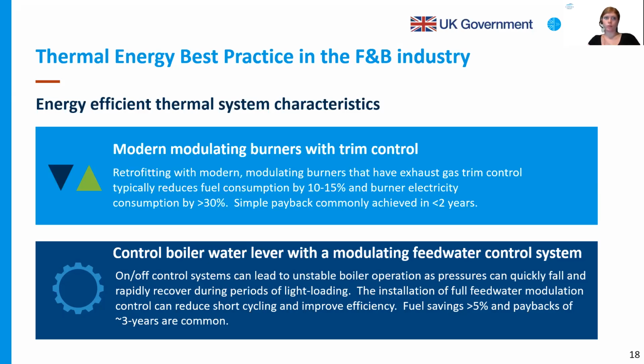The first one is modulating burners, which have exhaust trim control and also control the flow of fuel with regard to the coil outlet temperature and the heat load that is required. These modulating burners help to reduce fuel consumption by 10 to 15%, and the payback period could be realized in around 2 years.